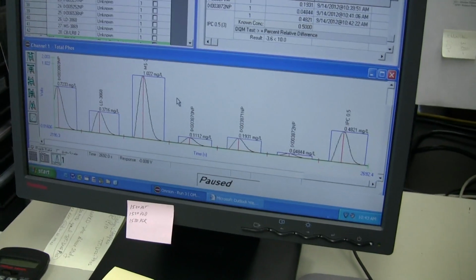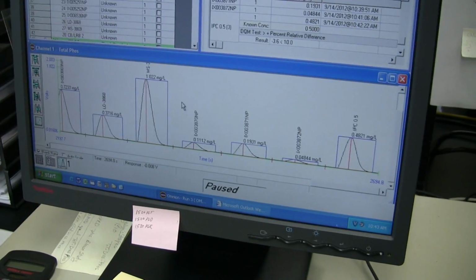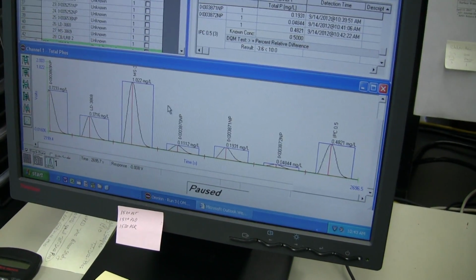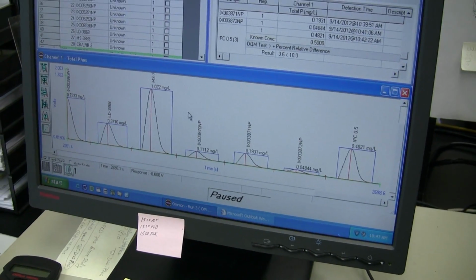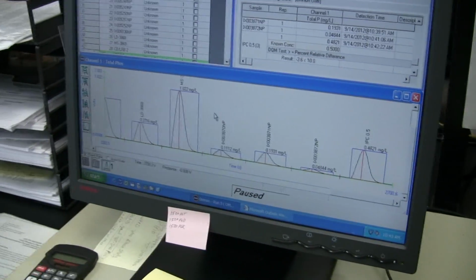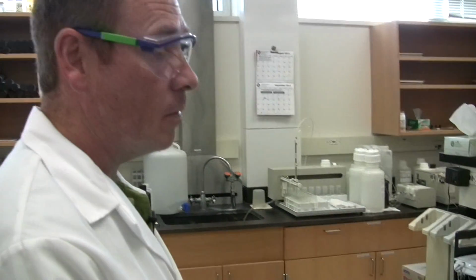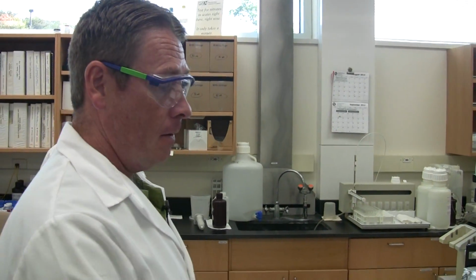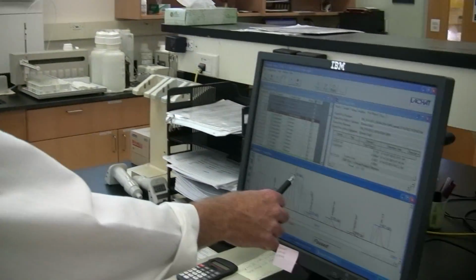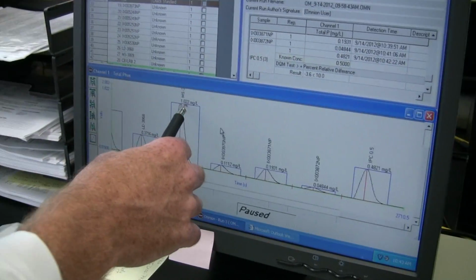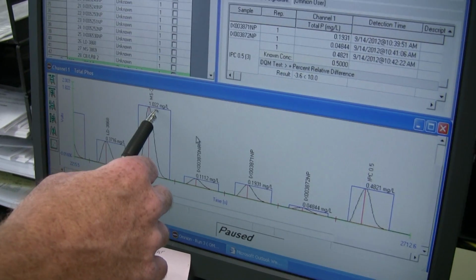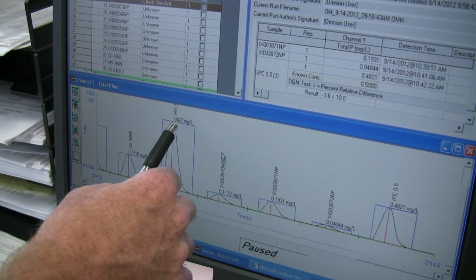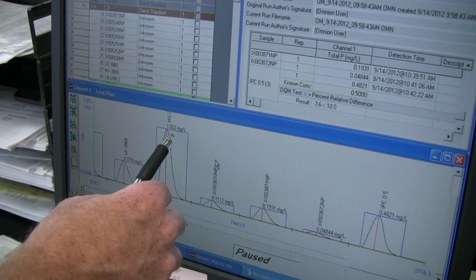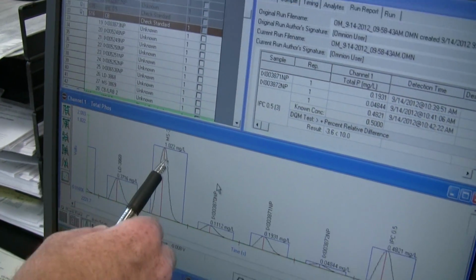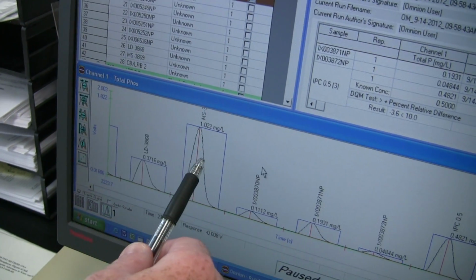We have the instrument running, and it seems to be running well. We'll let it continue. It's 186 cups, or test tubes, whatever you want to call it. A cup is what we refer to as the position number, but you can think of it as the test tubes in the rack. Something interesting, this one is actually over 1, so I'll have to do a dilution and run that at the end so it's within my calibration range, which is, once again, from 0 milligrams per liter to 1 milligram. And since that's greater than 1, I'll have to rerun that with a dilution.